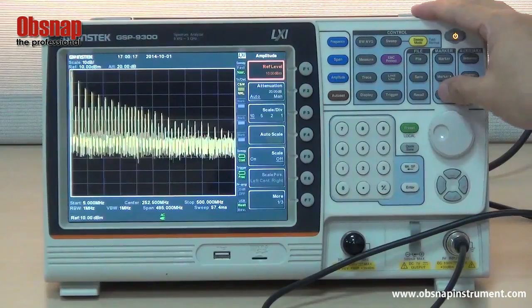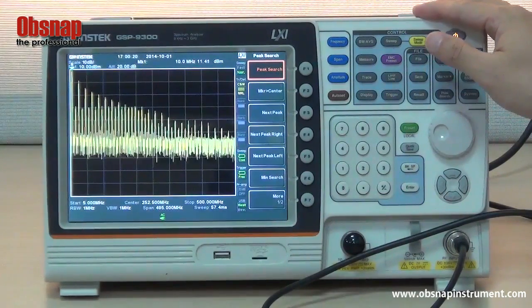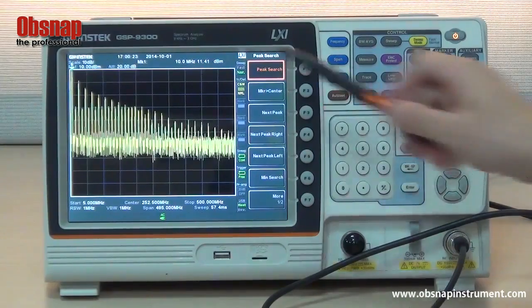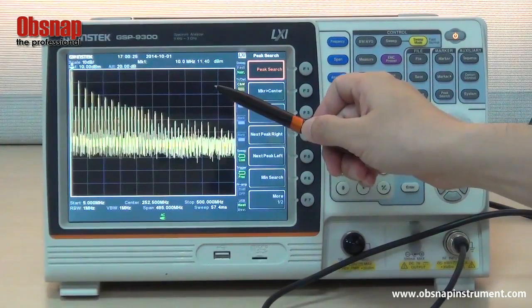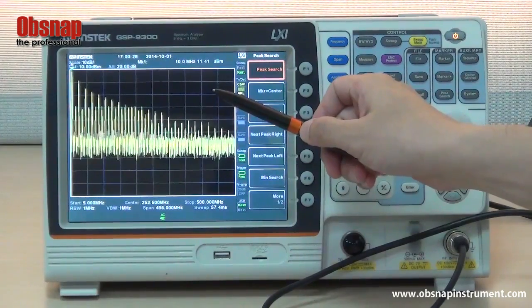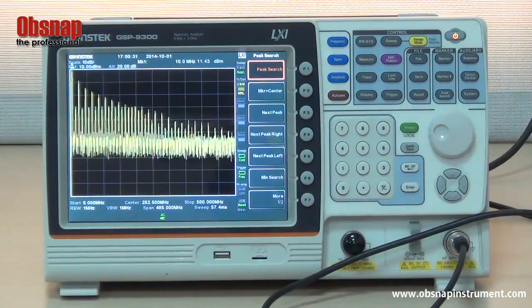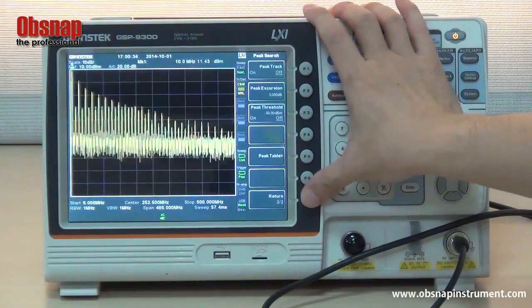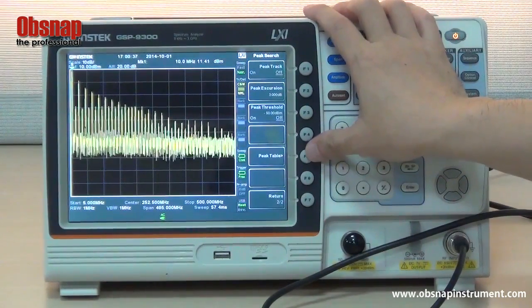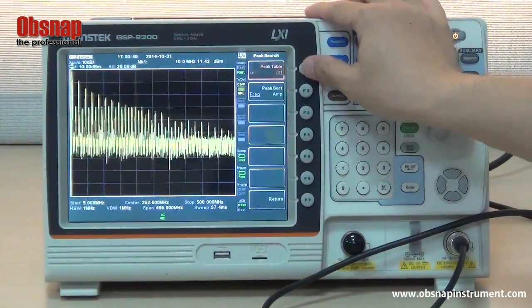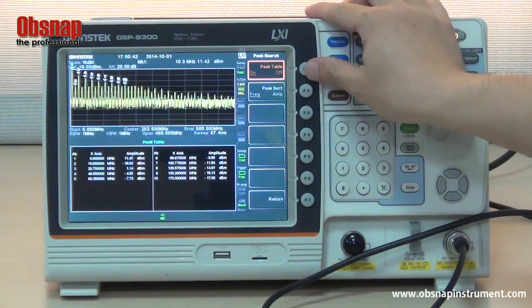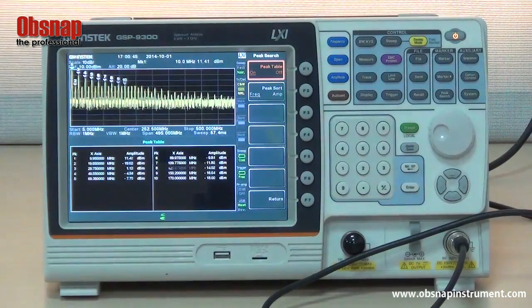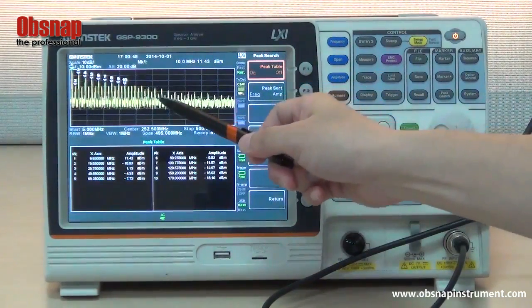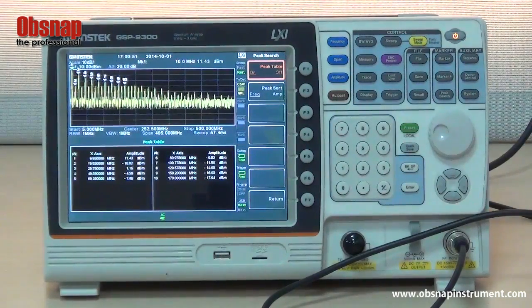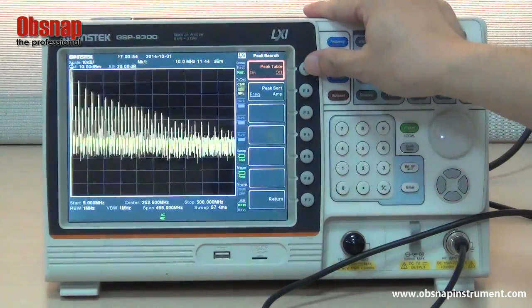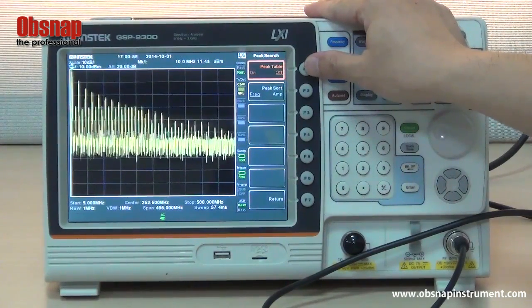Next, press peak search to rapidly search the signal's peak value. Now, a marker is shown on the screen displaying the 10 MHz frequency and power value. Next, press F7, more, and F5, peak table, and F1, peak table twice to activate the peak value table and automatically search 10 harmonic signals. Next, press F1, peak table, to turn off the peak table function.